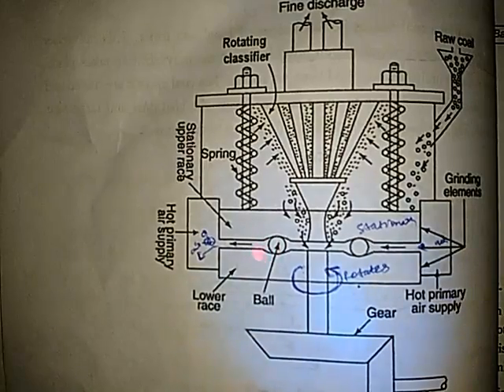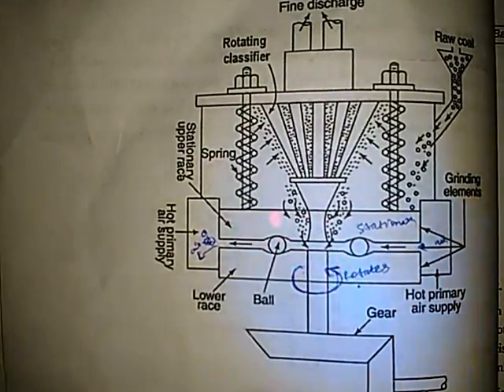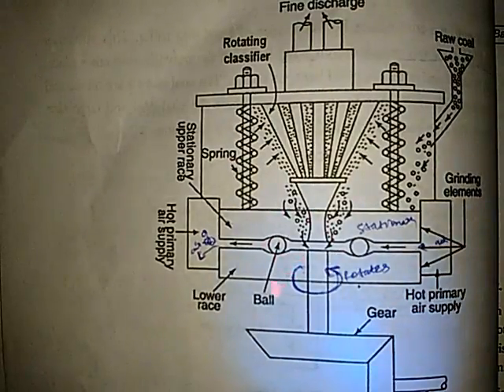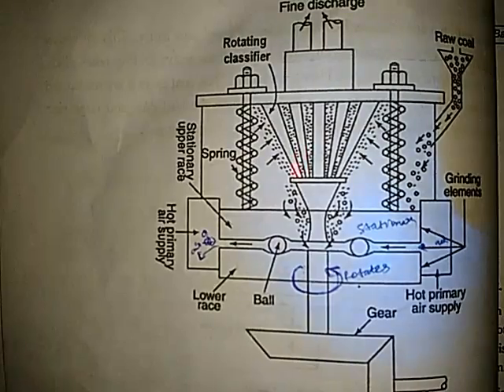The coal is crushed in this portion. After the crushing of the coal, the powdered coal is taken to the rotating classifier. This rotating classifier works on the principle of centrifugal force where the larger coal particles are separated at its ends due to their larger mass.